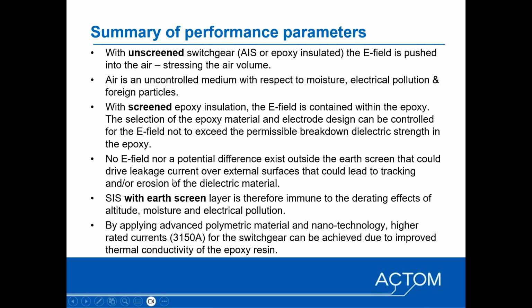No electric field nor potential exists outside the earth screen that could drive leakage current that could lead to tracking or erosion of the dielectric material. And with solid dielectric material with an earth screen layer, it's therefore immune to the degradation effect, or derating effect, of altitude, moisture, and pollution. And with the application of advanced polymeric materials, we can achieve current ratings of up to 3,150 amps and 4,000 amps with additional forced cooling.